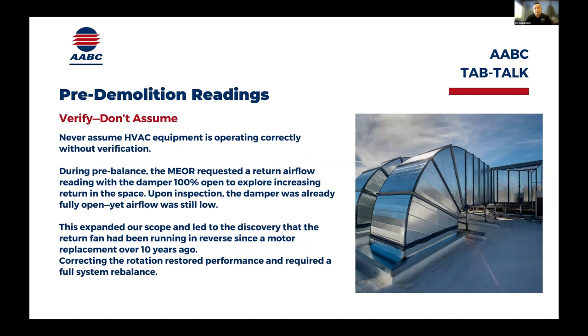We were incredibly low. I think they wanted 350 CFM. We were like 80. And they're like, can you make sure the damper's open? So we opened up the damper. It was already 100% open. So we had to explore and continue to explore, okay, what's going on with this return system, right? Is there a closed fire smoke damper? What else is going on? How is this one diffuser supposed to be 350, only 80, and we need 80 CFM more than that at the post balance? Well, that led us all the way to the air handler.